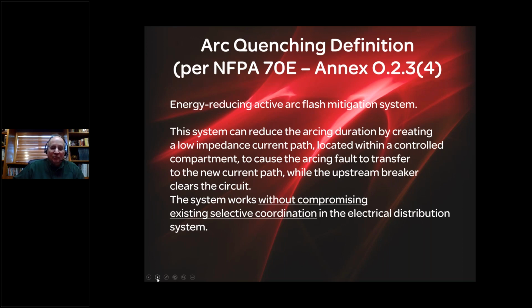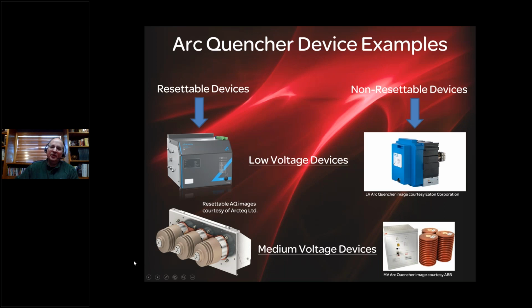Our particular system is nothing more than a very powerful electrically withstand rated electromagnet, which is resettable like a circuit breaker. So these are some arc quencher device examples. The devices shown on the left are resettable devices, just like a circuit breaker. And here are some examples on the right, both low voltage and medium voltage, of non-resettable solutions. The Eaton device shown is a one-time use device. The ABB device is quite unique. The UFES, the ultra-fast earthing switch, I call automotive airbag technology. It's a one-time chemical discharge out of those canisters. Those canisters that look like insulators are the actual shorting devices.